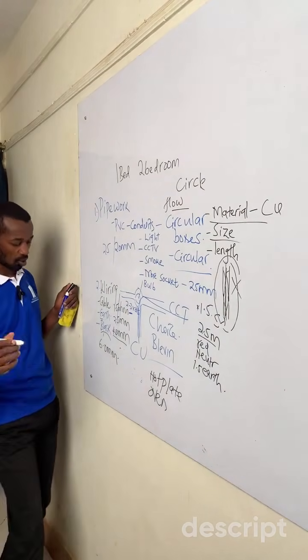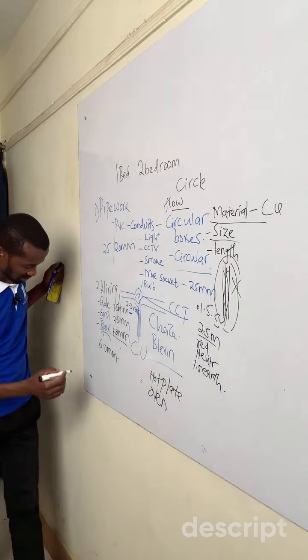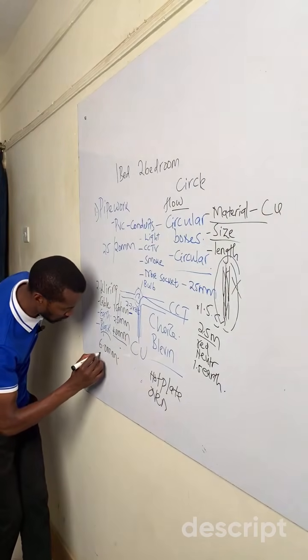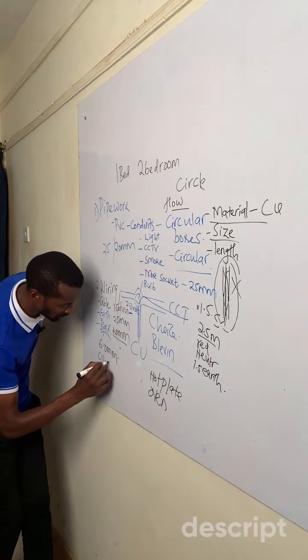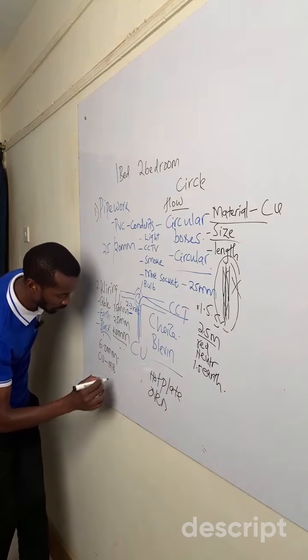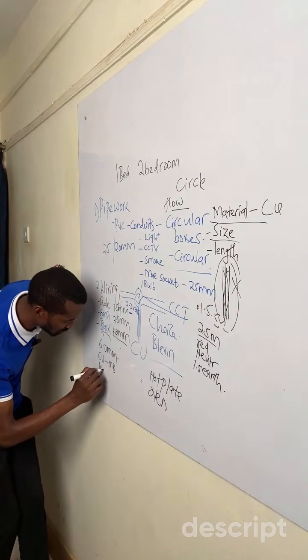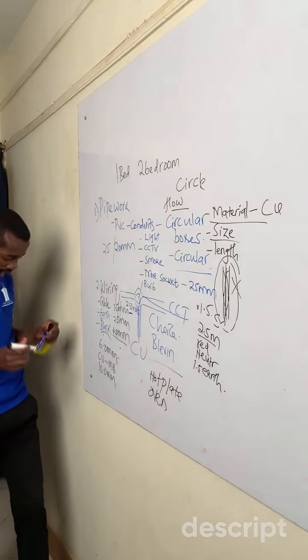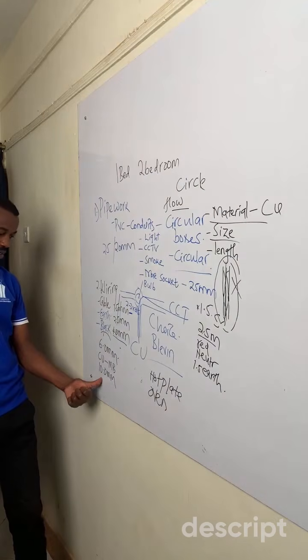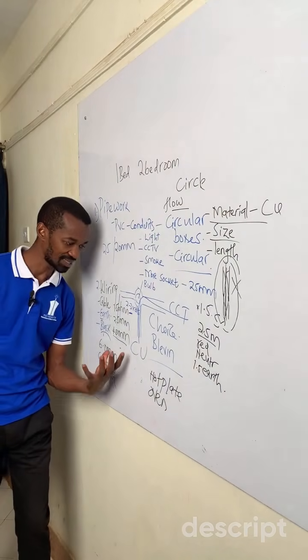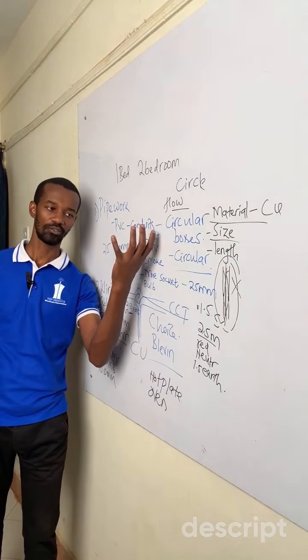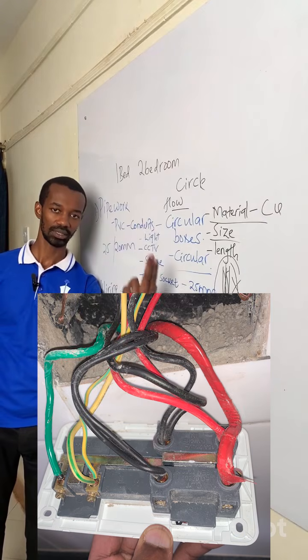Now another important thing we need to know is that for a consumer unit to a meter box or meter board, we require a 10mm cable. Why? Because this one will definitely be sustaining all of these loads from the lighting, sockets, shower heads, as well as the heaters.